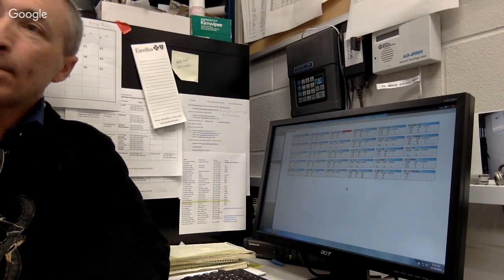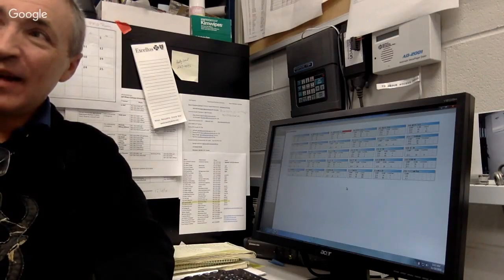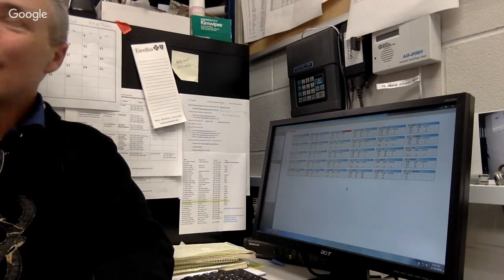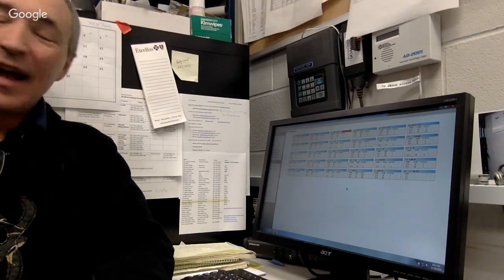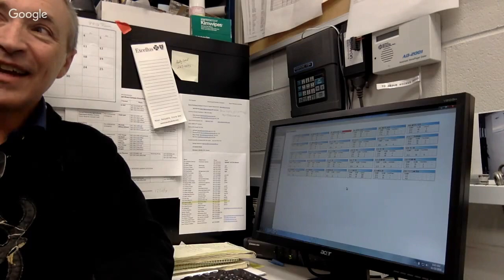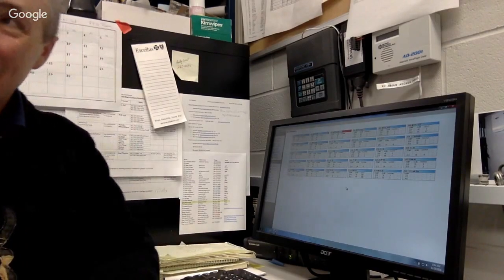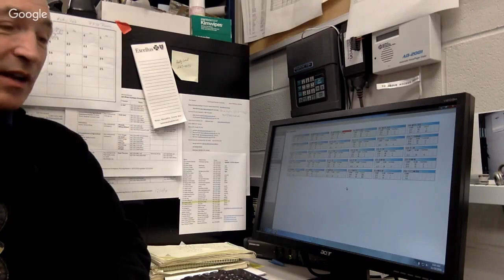If something goes wrong, do you get a call at home? Yes — one of the benefits of our system is that these growth chambers and greenhouses are alarmed and they directly dial my home phone and my cell phone. It'll keep dialing and emailing me until I respond. So yes, it could be the middle of the night — many times, even on Thanksgiving. Sometimes it's as simple as a researcher was warm and opened a back vent, but it got cold at night and went off on a low temperature alarm. Fortunately, I can access these from home, close the vent remotely, and go back to bed. But sometimes we have to come in. So some of the stuff in the greenhouses you can actually control remotely — very good control systems.